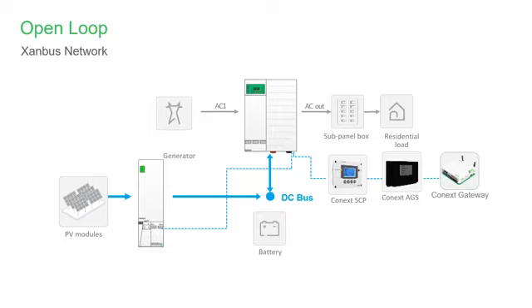So let me explain what I mean by open loop and closed loop integration. So in an open loop integration, the battery is a lead acid replacement. It means that it just simply behaves like a lead acid battery, and it doesn't have to have any type of communication with the Xanbus network. It accepts the voltage, the battery manufacturer will give us the set points, we program the set points, and that battery will behave just like a lead acid battery.